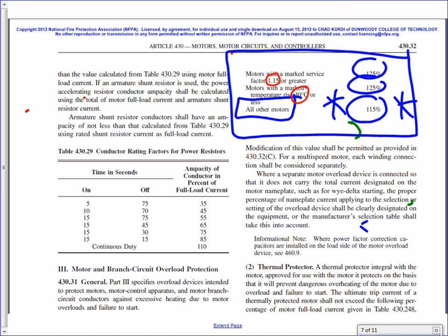Okay? Temperature rise 40 or less. This will tell you that the windings have been sized so that the temperature will not rise more than 40 degrees above the ambient temperature. Unless you hear these two, temperature rise and service factor, what's your default? 115. Math, does it make sense? I know some others have seen this before. Your job, guys, is to highlight this one and keep it handy for future use.